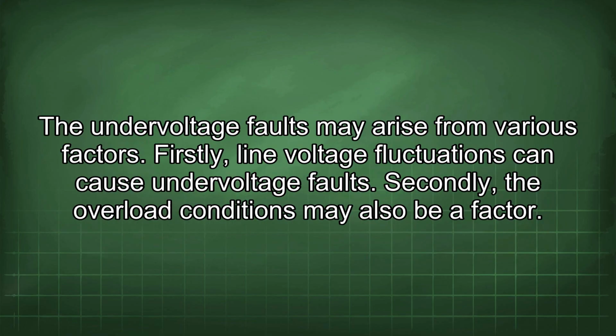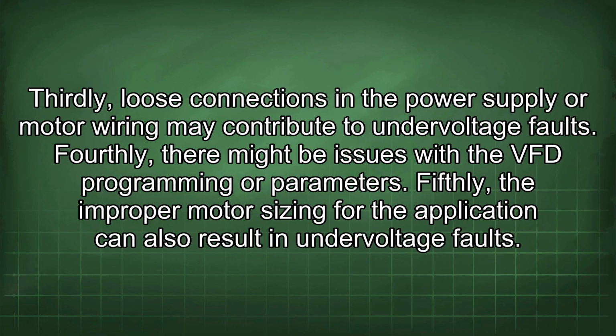The undervoltage faults may arise from various factors. Firstly, line voltage fluctuations can cause undervoltage faults. Secondly, the overload conditions may also be a factor. Thirdly, loose connections in the power supply or motor wiring may contribute to undervoltage faults. Fourthly, there might be issues with the VFD programming or parameters. Fifthly, the improper motor sizing for the application can also result in undervoltage faults.